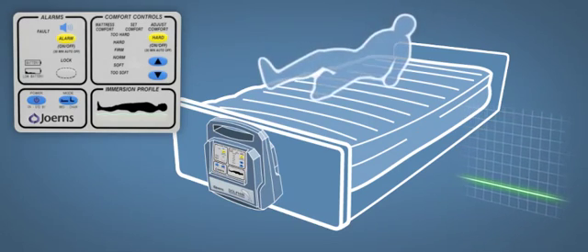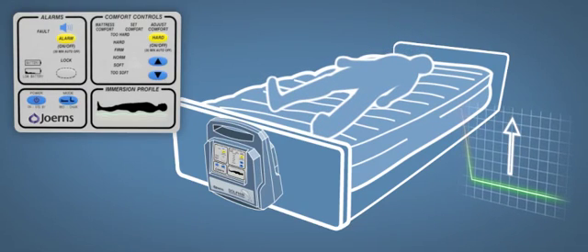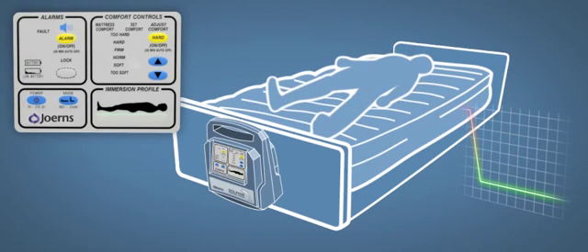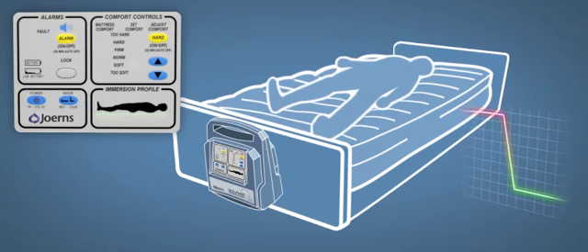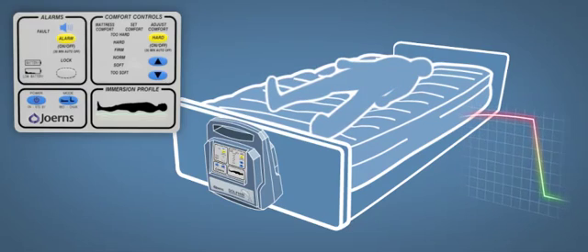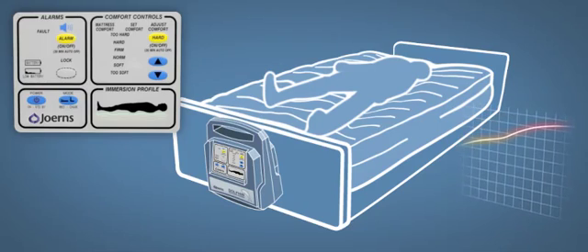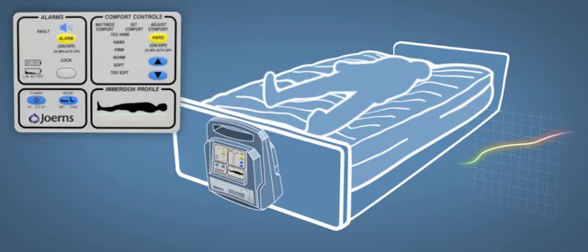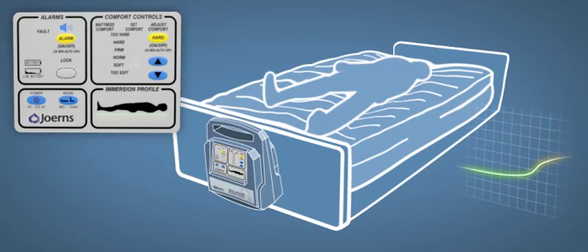As the patient is placed on the firm surface, you will see the percent of occlusion rise as the surface begins to calculate the patient's weight. Within seconds, the Dolphin FIS system automatically calculates the exact settings needed to ensure the proper surface laxity and air density customized for this particular patient's weight and body surface area. By looking at the graph, you can see the occlusion levels drop and finally achieve an equilibrium state.